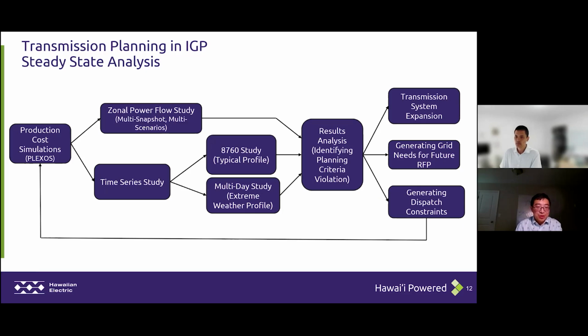In addition to that, we also evaluate extreme weather conditions, such as long duration days with very low solar energy production, where the system may need to use batteries more than normal. So we got those extreme weather profiles and production simulation data under these extreme weather conditions, and also run time series studies to make sure the transmission grid has enough capacity to let the system dispatch in that way.